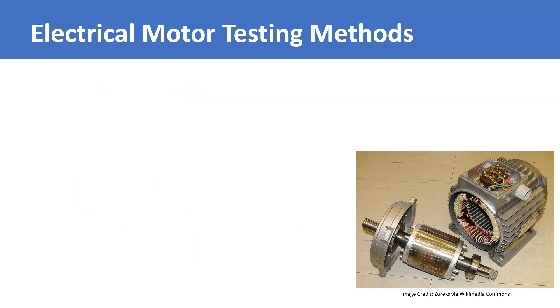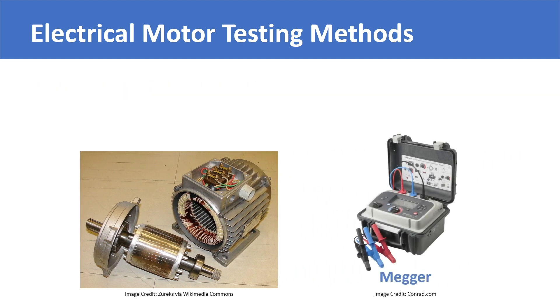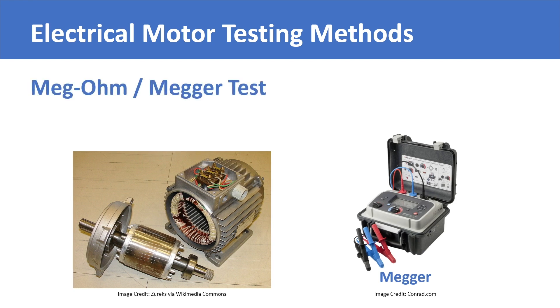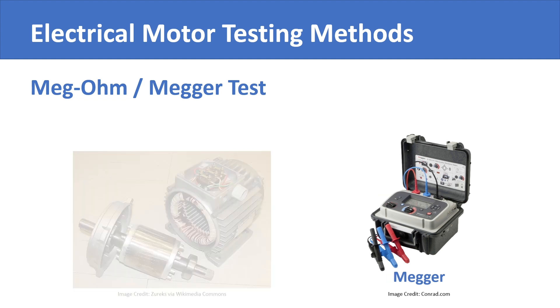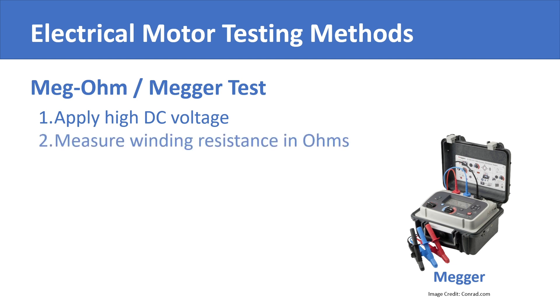Another similar test is the Megohm test. It is performed by a Megohm meter, simply referred to as a Megger, that tests the health of the winding insulation. It does so by subjecting the motor to a very high DC voltage and measuring the resistance of the winding in ohms. In case the winding insulation health is compromised, a low ohm reading will be observed.